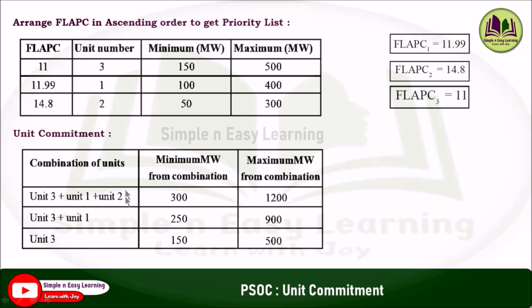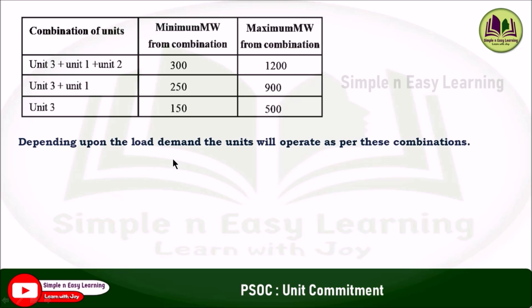The unit commitment combines units based on priority. Combination 1: unit 3 + unit 1 + unit 2, with minimum 300 MW and maximum 1200 MW. Combination 2: unit 3 + unit 1, leaving out the least priority unit 2. Combination 3: unit 3 alone, with its minimum and maximum limits. This unit commitment table determines which units operate based on load demand.